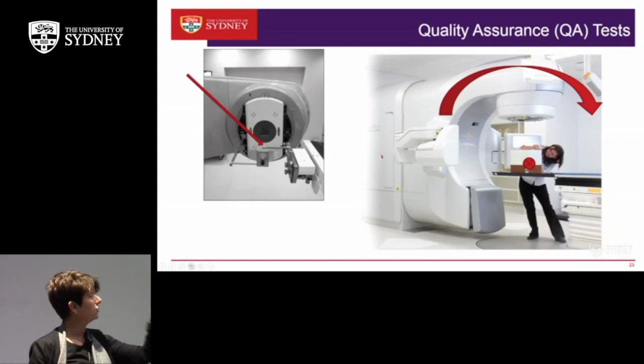So the radiation is coming out of the head. The ball bearing is here, and we have some film here. So when the radiation comes out, this is what you see on the film. So this is the radiation that's coming out of the head, which is a square block, and this is the shadow of the ball bearing. Now, if the ball bearing is actually at the isocenter, it will be in the center of that square. And you can see it's a little bit displaced, but not very much, less than a millimetre.